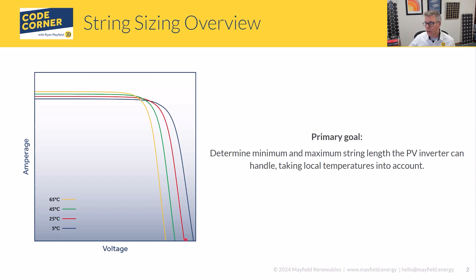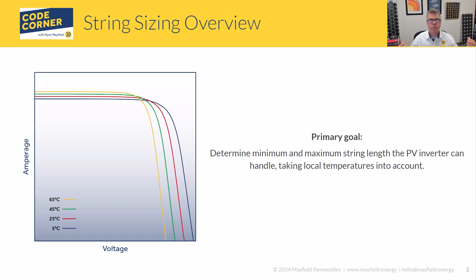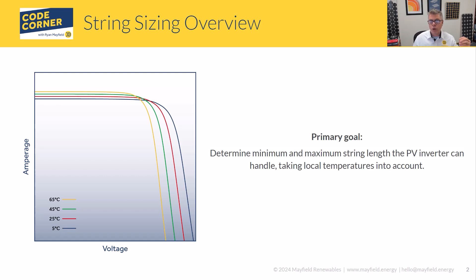On the flip side, as it gets colder, the module open circuit voltage increases. These are important aspects to know about because as you are sizing your strings, you need to look at two different things. You need to look at the open circuit voltage when it's really cold — middle of winter, sun pops up, array is cold — that voltage is going to be put onto the terminals of the inverter, and we need to know what that is. We also need to know in the middle of summer, when the array is operating at an elevated temperature, what that maximum power voltage is. So you're going to look at both sides of it.